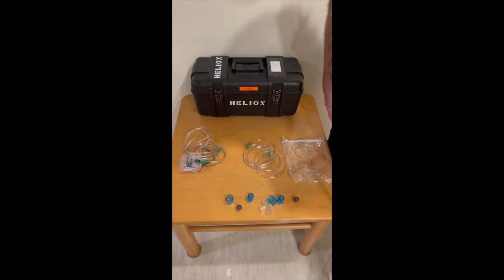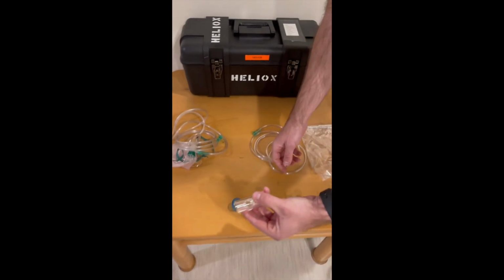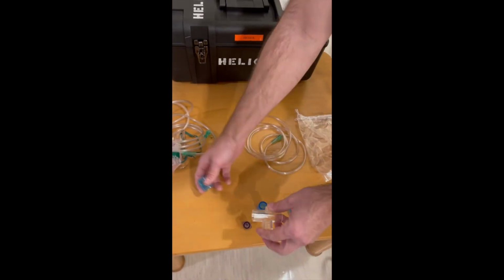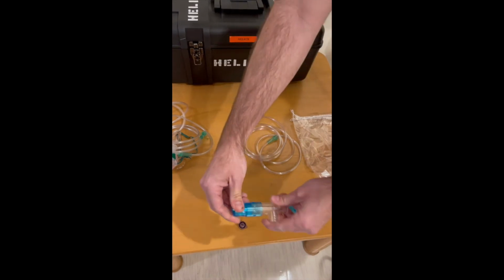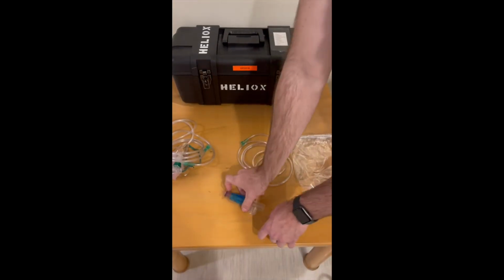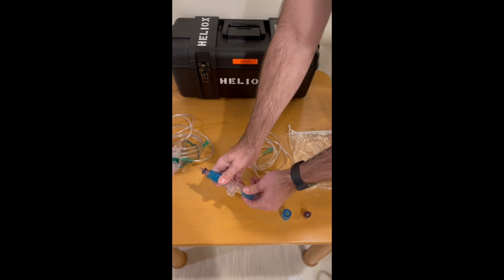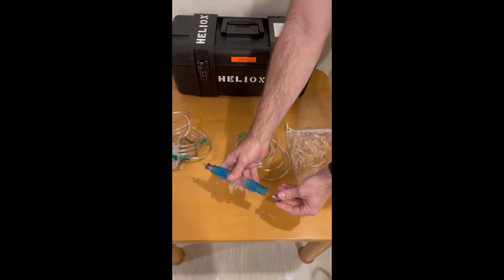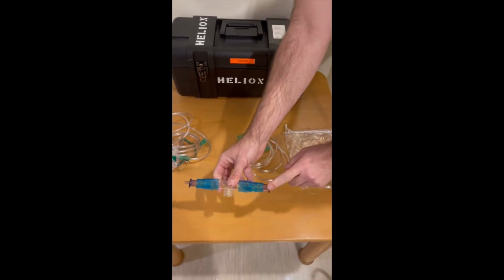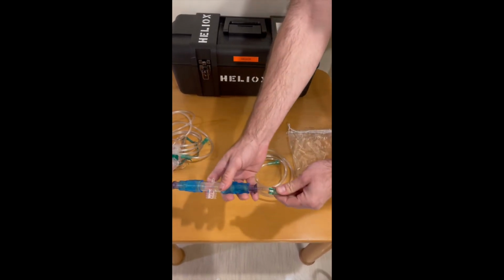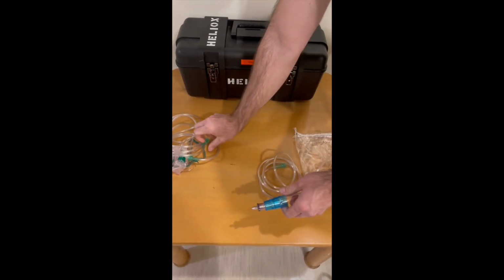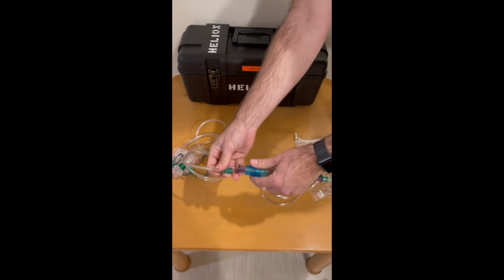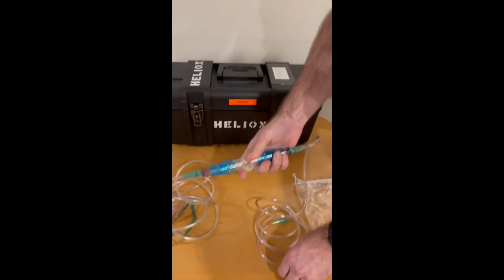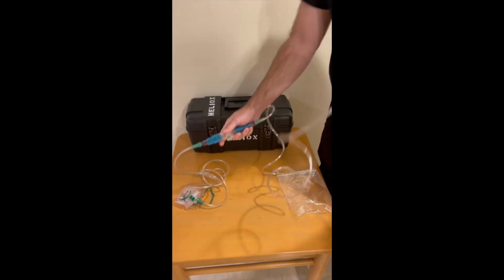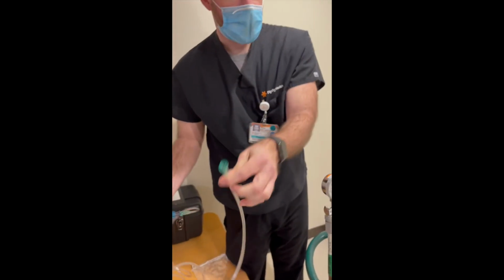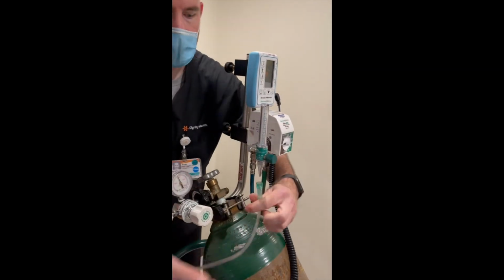We'll now assemble the patient interface. You'll have a T-piece, 22 adapter, 15 adapter, nipple adapter. And on the other side the same, 22, 15, and a nipple adapter. On this side, we will connect the oxygen tubing. On this side, we'll connect the non-rebreather tubing. The oxygen tubing will be placed onto the oxygen flow meter.